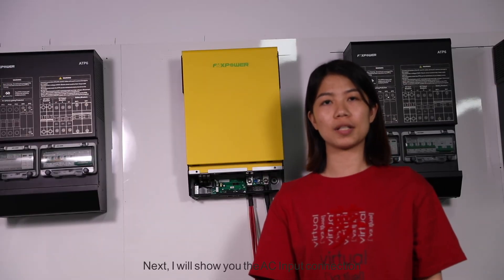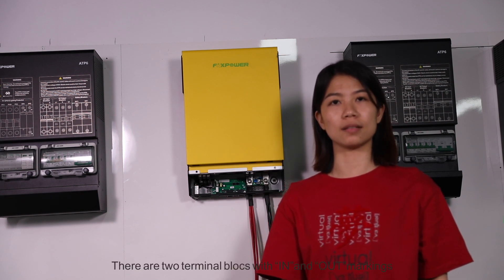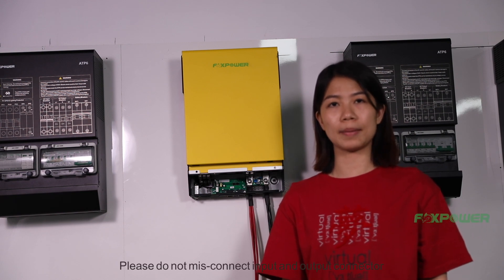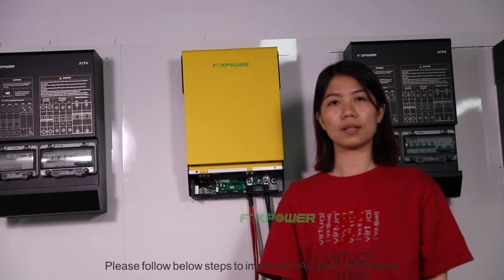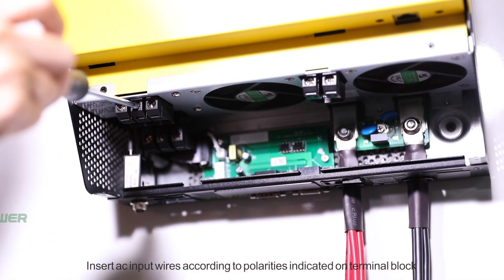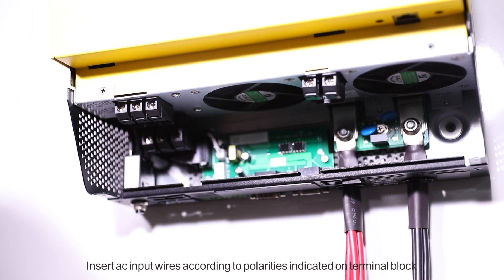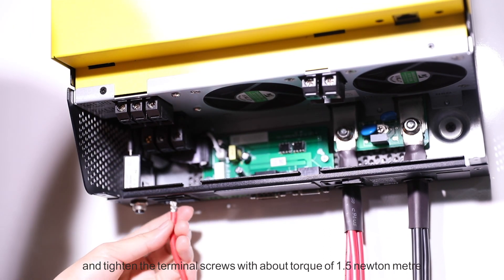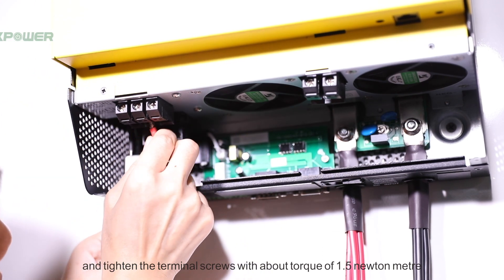Next, I will show you the AC input connection. There are two terminal blocks with IN and OUT marking. Please do not misconnect the input and output connectors. Insert AC input wires according to the marking indicator on the terminal blocks and tighten the terminal screws with a torque of about 1.5 Nm.